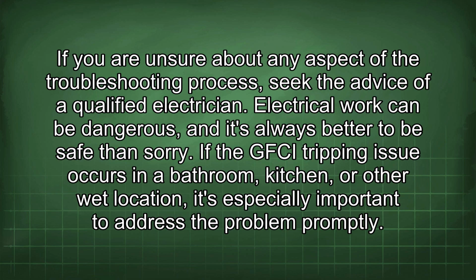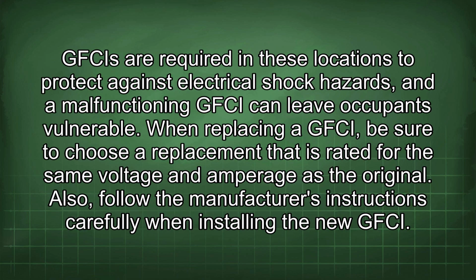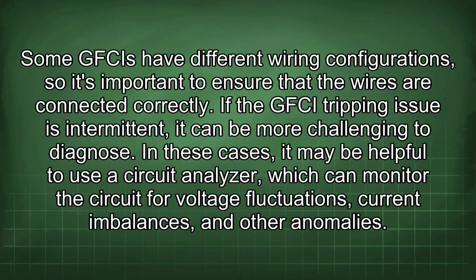If the GFCI tripping issue occurs in a bathroom, kitchen, or other wet location, it's especially important to address the problem promptly. GFCIs are required in these locations to protect against electrical shock hazards, and a malfunctioning GFCI can leave occupants vulnerable. When replacing a GFCI, be sure to choose a replacement that is rated for the same voltage and amperage as the original. Also, follow the manufacturer's instructions carefully when installing the new GFCI. Some GFCIs have different wiring configurations, so it's important to ensure that the wires are connected correctly.